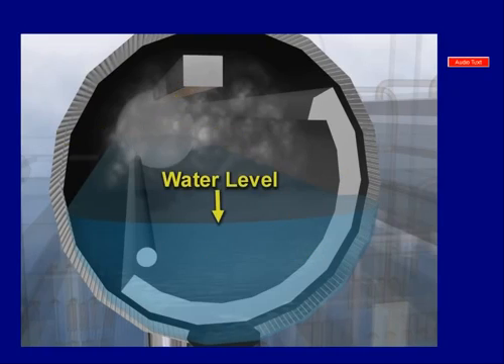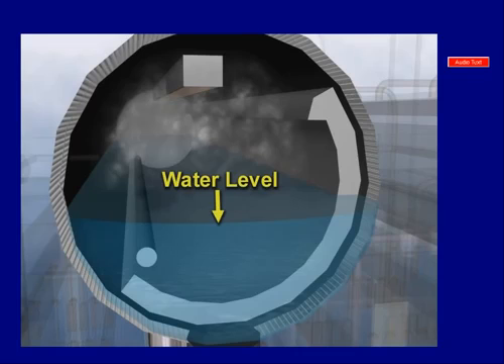The LP, IP, and HP drums are designed to contain the expansion, or swell, of their individual evaporators, which occurs during start-up due to the expansion of water that is being heated.